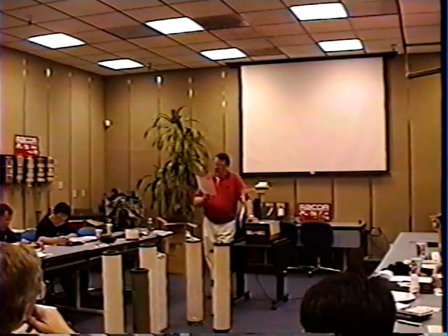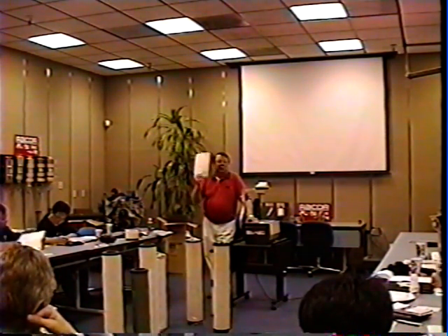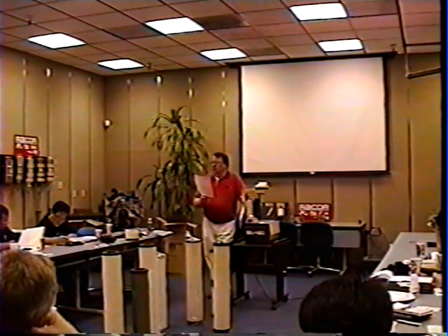When we first came out with our VVFS, now called RVFS, we had ratings up to 150 gallons a minute, but that was done with jet fuel and kerosene, which you must derate 50% for diesel fuel. And it got real confusing. So on all of our new brochures, we show different ratings for the most common fuels that we run into. And that's why we say weights and volumes are approximate. Consult factory for any unusual fluids that they may be filtering, because as we all know, different fluids have different viscosities, and that does different things to your elements and your flow rates and your filtration abilities.